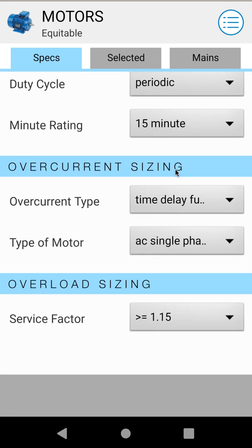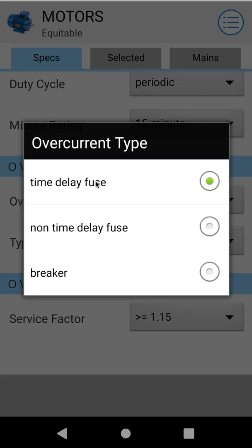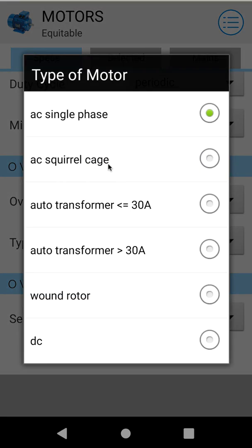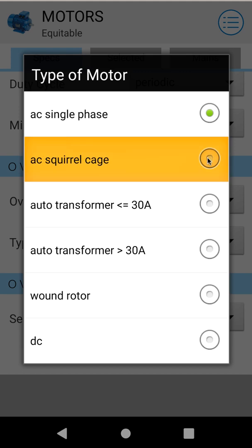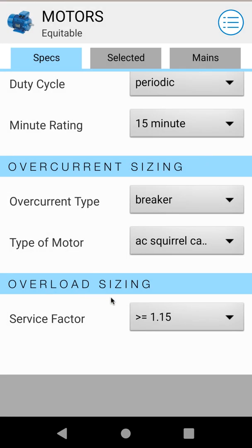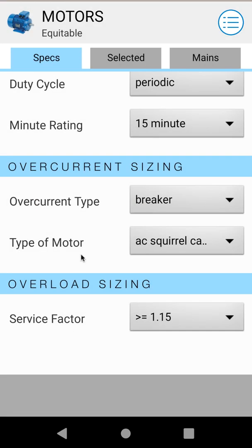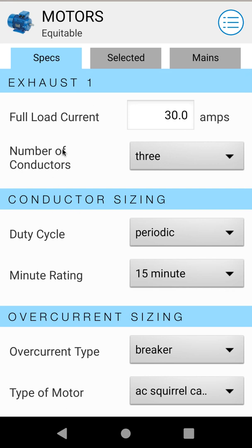Then we'll move down to overcurrent sizing. These selections affect your overcurrent sizing. We choose from a time delay fuse, non-time delay, or breaker — so let's say we're using a breaker on this one. Our type of motor we'll go with AC squirrel cage. And service factor, which affects your overload sizing — your only two options are greater than or equal to 1.15, or less than 1.15. So let's go ahead and leave it on greater than.